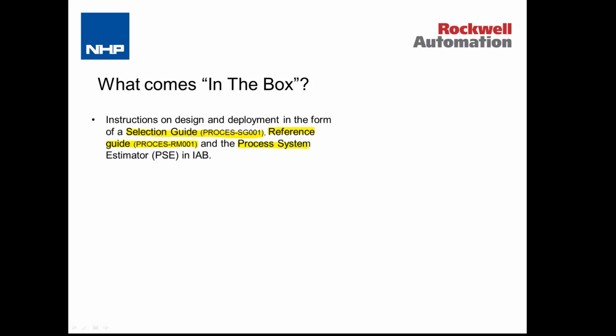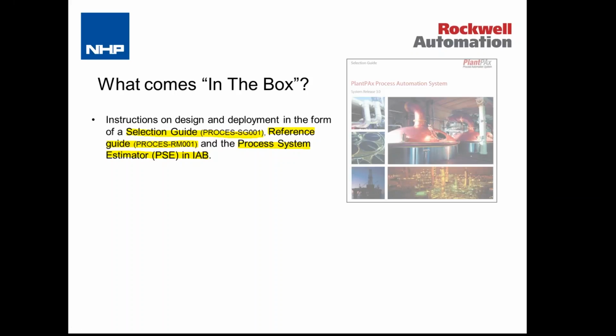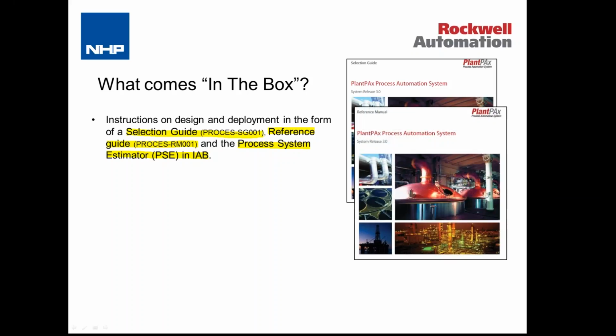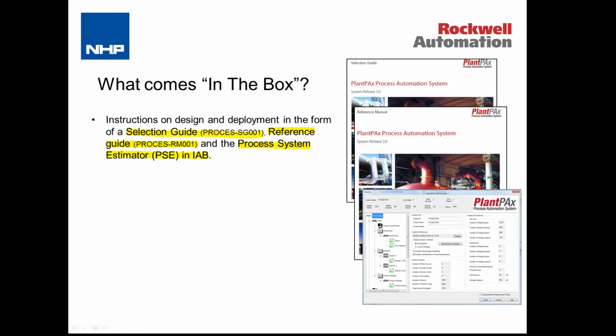And the final piece that we have in terms of assisting us in design of the system is the Process System Estimator in Integrated Architecture Builder. So this is a tool that allows us, at the point where we have an I/O count, to determine the performance of the system, and allows us to select the correct processor, the correct I/O arrangement, the correct network, the FactoryTalk View configuration and environment, to make sure that the system is going to meet the performance criteria that is required. So there we see the selection guide, the reference manual, and the Process System Estimator in Integrated Architecture Builder. That's one of the wizards. If that's something you're not familiar with and you would like to become more familiar with, then certainly that's something that I can help you with outside of this presentation. More than happy to come and meet with you and work through the use of IAB and the Process System Estimator.